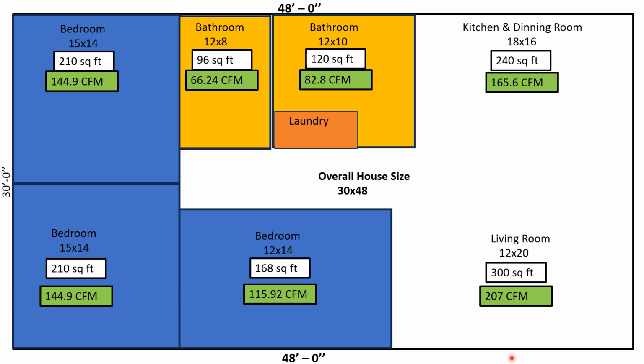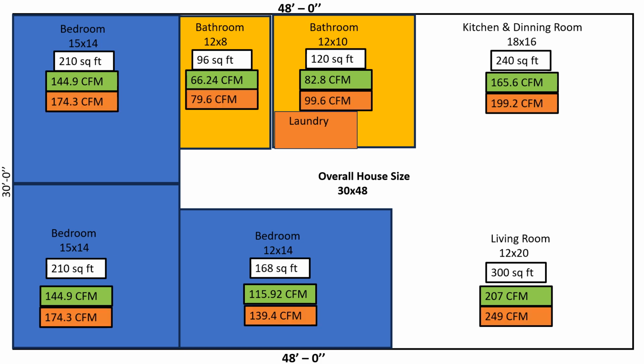But we decided we were going to go with a 3-ton. So if you look at the numbers in orange, that is the CFMs that you would use for a 3-ton. Now see how things have changed. So now I've got options in the bedrooms, in the living room, and in the kitchen area, because our numbers changed since we went with a 3-ton. So we had to take 1,200 and divide that into 1440, which is the square footage of our house, and our number was 0.83. And like I said, the Slide Cool Rule uses a 0.80 across the board, and that works as long as everything else works out.